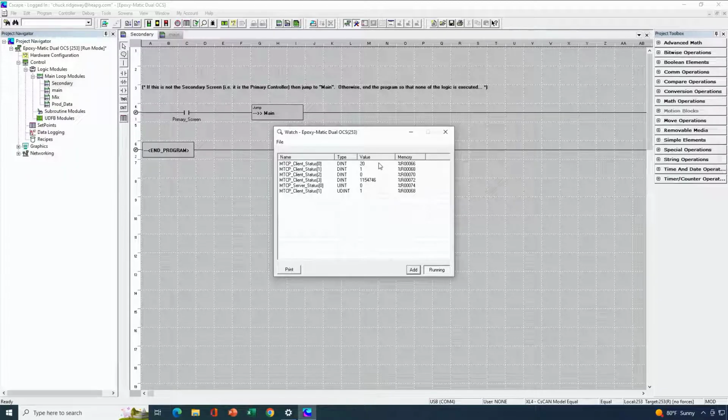So you can certainly, for a modest application, a small application really, do way, way better than 100 milliseconds even. And if you're efficient in the way that you map your variables, you can probably accomplish sub 100 millisecond response even for a larger application. Certainly, you can keep it below 1 second. So hopefully that was enlightening.